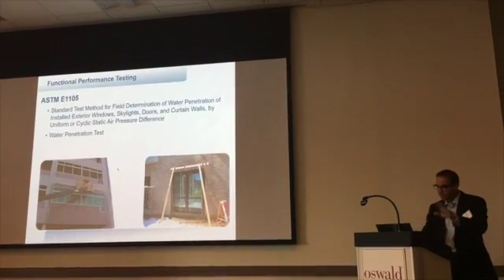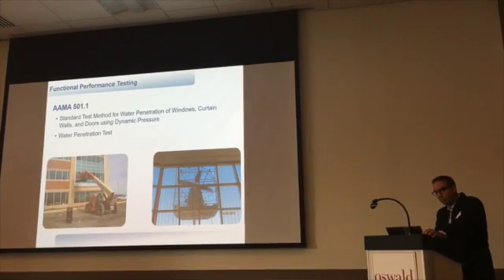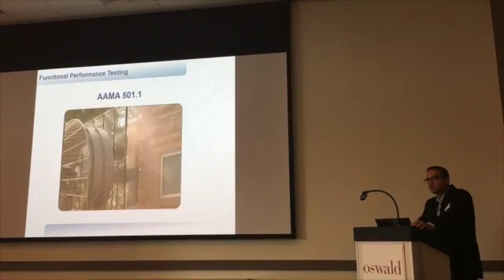Switching from air to water testing now. The ASTM E1105 is a very common test — just a spray rack on the outside, a chamber on the inside, with a constant vacuum drawn. More and more, especially on the commissioning front, we're getting into dynamic testing — spraying water on the outside — which is as close to a nor'easter as we can get as an industry. There is tremendous value when our testing can simulate Mother Nature: we're not getting false positives, we're not over-testing, and most importantly, we're getting a good level of assurance that when Mother Nature tortures this building, we're in good shape.